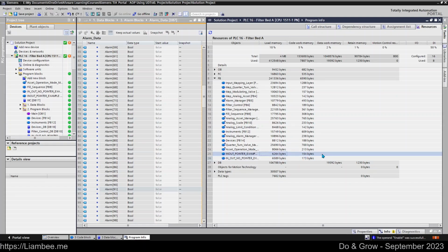But we've only got 3 lines of code, and we're not really dealing with a great deal of data. So when you start having big structures, like for all of your different assets, or a system that comes together out of lots of different assets and they're all bundled into one big UDT, passing by reference through an in-out interface makes a big difference.